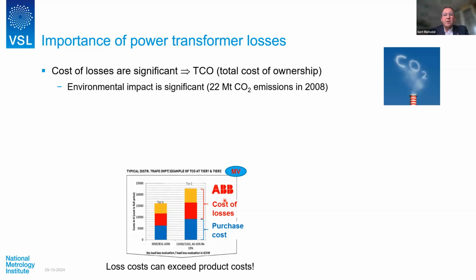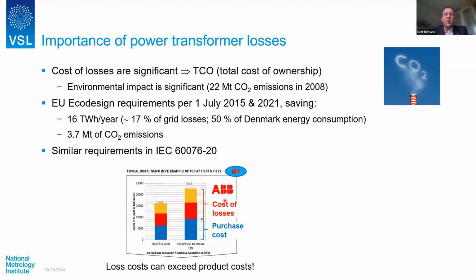So that also relates to CO2 emissions and an environmental impact. So that was also recognized in the EU, where they did an impact study and found that the losses of the power transformers in the grid in the EU amount up to half of the energy consumption of a complete country, Denmark. So this is just one component, power transformers, and a very significant amount of total losses. So that's why they said, okay, we want to limit these losses. And in order to achieve that, they said we'll put requirements on the minimum efficiency that a power transformer should have. So by now, already for more than 9 years, there are hard requirements on the efficiency of a power transformer in order to be allowed to install it in the grid.